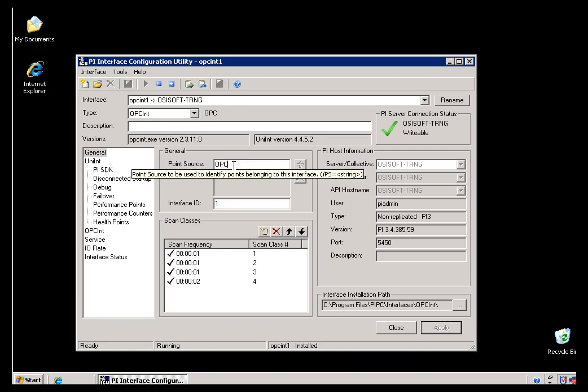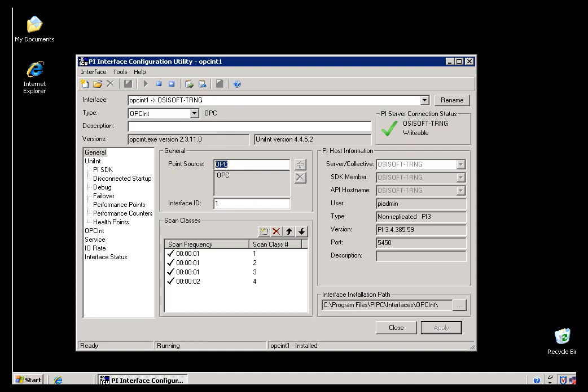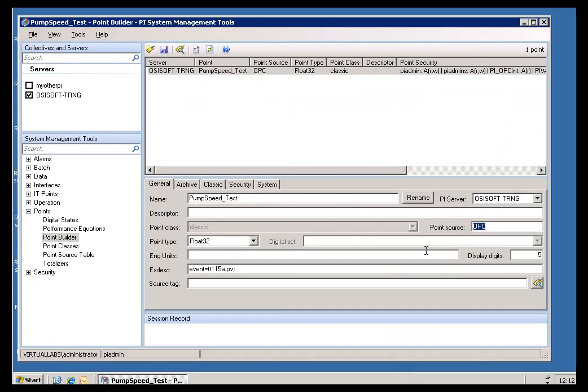There's a certain cycle that goes on, kind of a major cycle of once every two minutes, we go out to check to see if there are tags. If the day that you create a thousand new tags that all use that OPC Point Source, it can take up to two minutes for the Interface to detect that, and it will go ahead and start processing them, but it will process them 25 tags at a time.